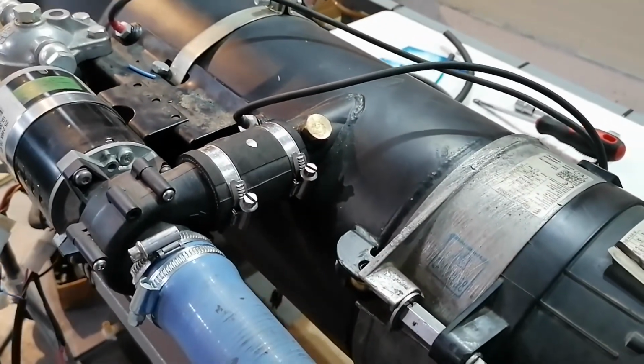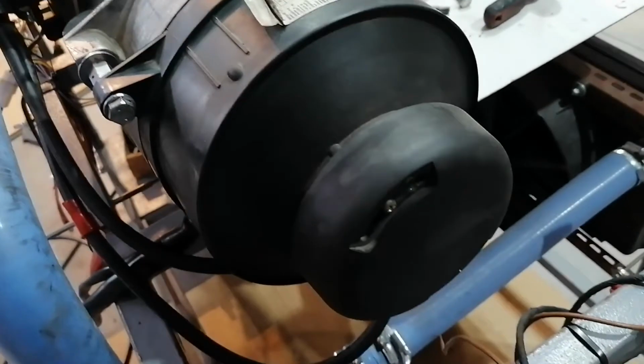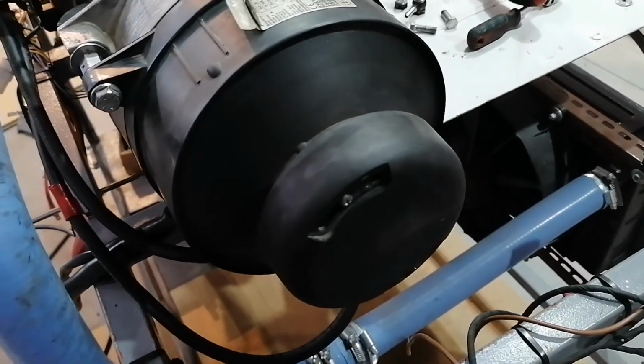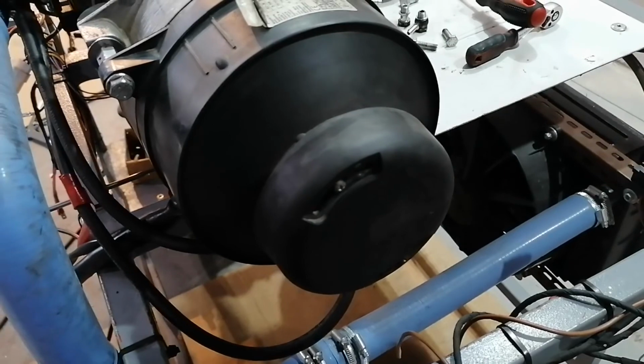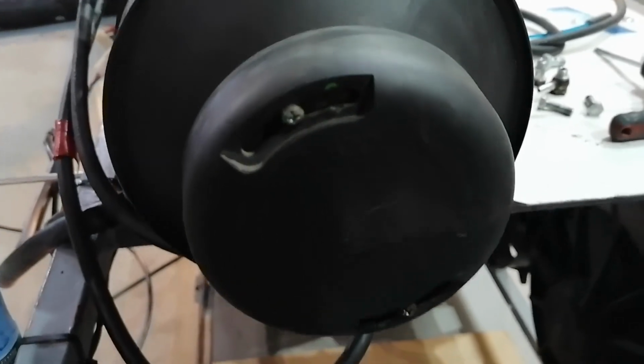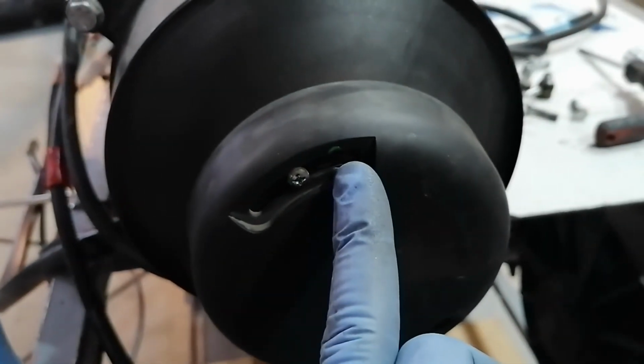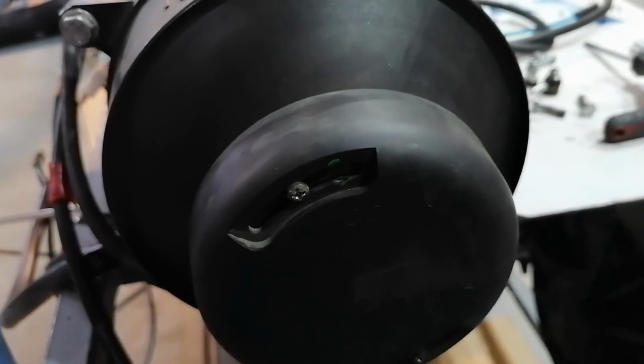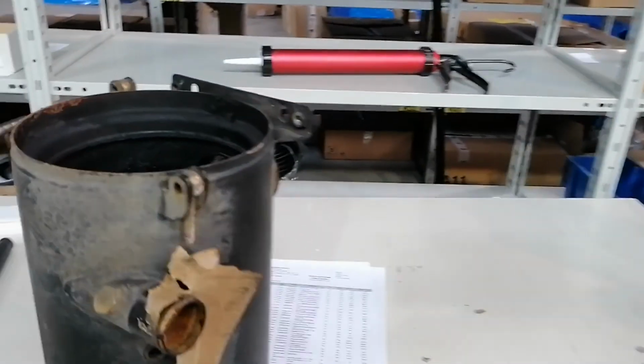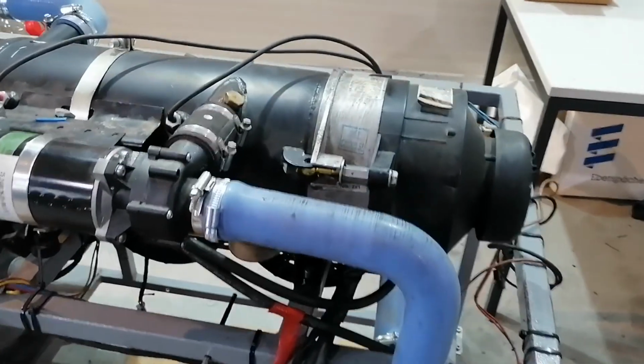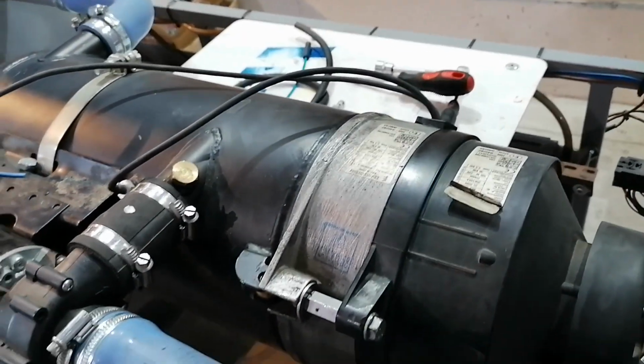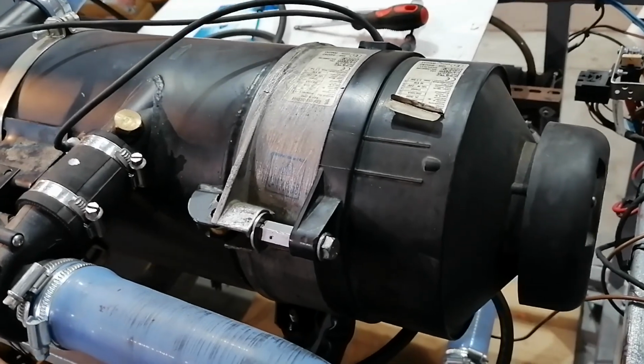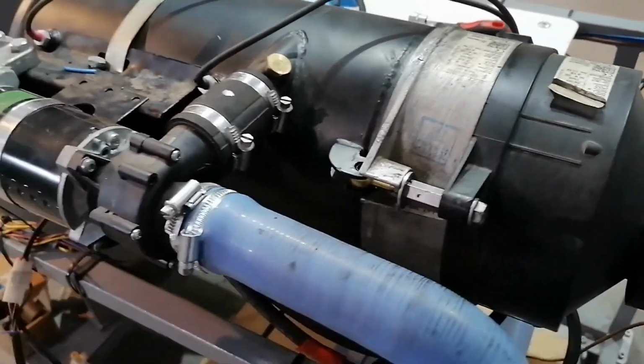The unit is working now, everything is repaired, so it was quite an interesting ride, but in the end everything is solved and the unit is working fine. We can see the difference in the CO2 setting - this is where it was when it came in, and this is now, so I'm pretty sure that all this blackness from the heat exchanger is because the unit was not burning the fuel correctly, and yeah, this just happened.